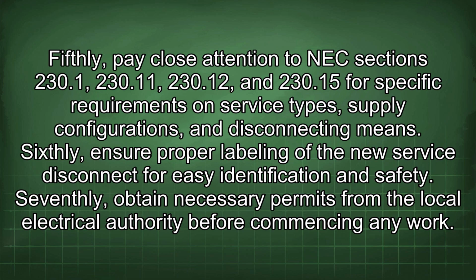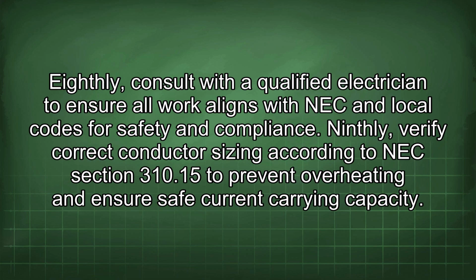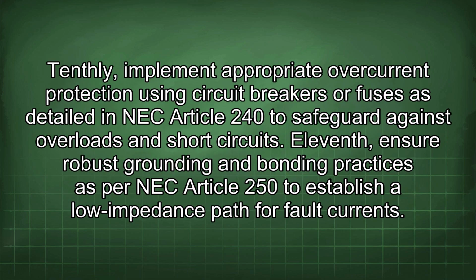Seventhly, obtain necessary permits from the local electrical authority before commencing any work. Eighthly, consult with a qualified electrician to ensure all work aligns with NEC and local codes for safety and compliance. Ninthly, verify correct conductor sizing according to NEC section 310.15 to prevent overheating and ensure safe current carrying capacity. Tenthly, implement appropriate overcurrent protection using circuit breakers or fuses as detailed in NEC Article 240 to safeguard against overloads and short circuits.